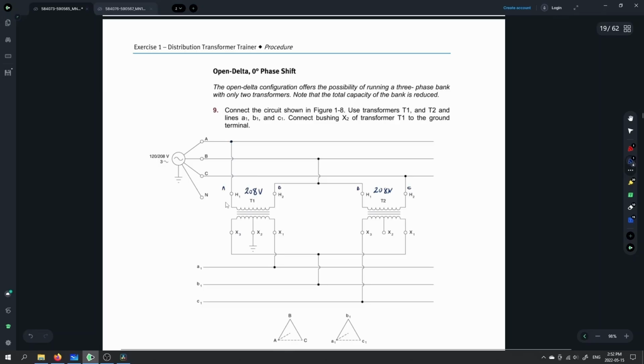We have H1 going to line A, so X1 is going to go to A as well if we're going to have this 0 degrees phase shift here. So you'll see on the secondary side that we have 120 volts on each of these guys. Because of the ratio, we have a 1.732 to 1 ratio, so the ratio of the transformer doesn't change whatsoever. Our secondary voltages remain at 120 volts.